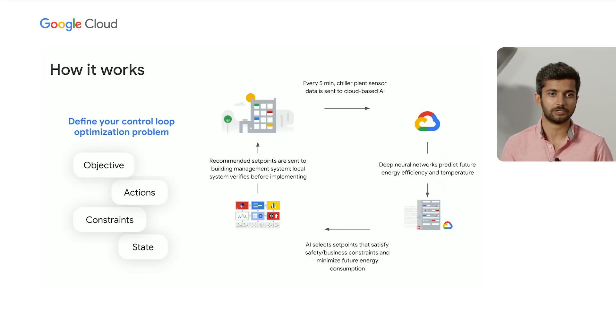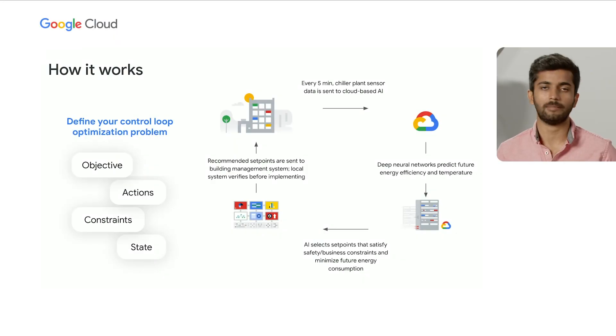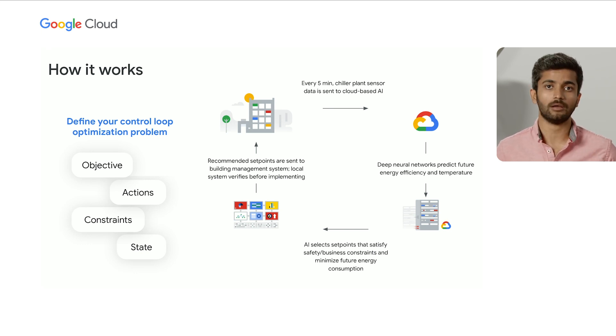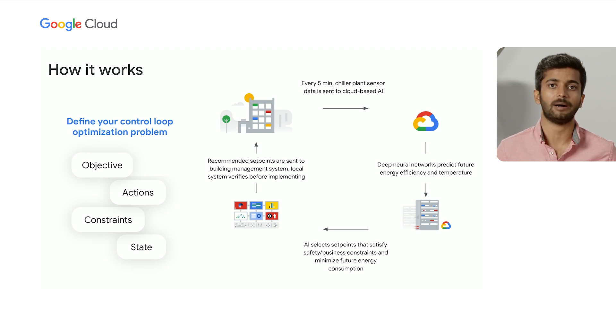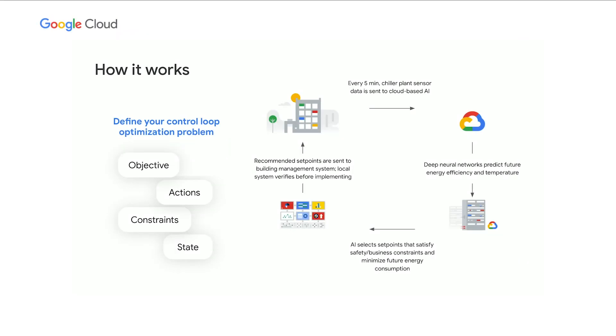And how does that work? The first step is that you define your control loop optimization problem in the template shown here. You define your objective function, which might be minimizing your energy usage over the next few hours, or reducing the batch time required to produce one batch of chemicals. Next, you make available actions to the AI agent that it can take to realize that objective — typically this takes the form of setting various set point values on your pieces of equipment. Next up, we have the constraints: these are the safety and business rules that the AI must abide by in order to operate your plant safely. And finally, you have the state — all the sensor data that tells the AI how the plant is currently performing.